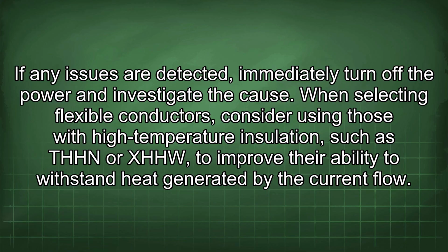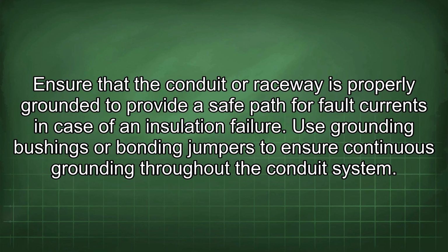When selecting flexible conductors, consider using those with high temperature insulation such as THHN or XHHW to improve their ability to withstand heat generated by the current flow. Ensure that the conduit or raceway is properly grounded to provide a safe path for fault currents in case of an insulation failure. Use grounding bushings or bonding jumpers to ensure continuous grounding throughout the conduit system.